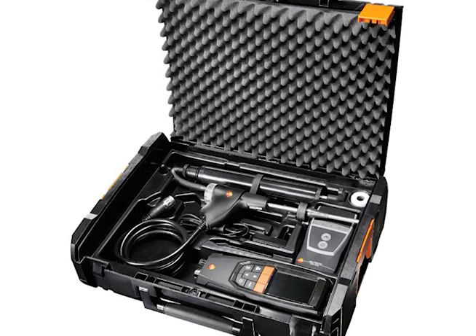Burner combustion must only be adjusted using a combustion analyzer. Do not attempt to adjust the burner by sight or sound. Do not attempt to adjust combustion based upon manifold pressure alone. Manifold pressure should only be used as a reference point.